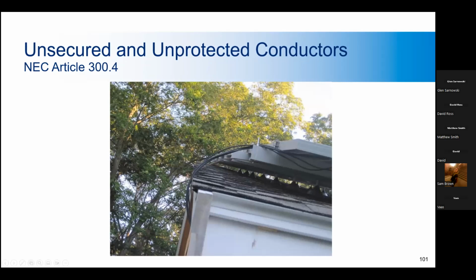Here we have examples of conductors that are not being protected from physical damage. You can see the sharp edge of the panels and the racking system, and also the roof, the shingles. The shingles are abrasive to the wires, and this should have been run through conduit to get around this edge. As it is now, they will rub on the shingles and will eventually wear away and cause the conductors to fail.